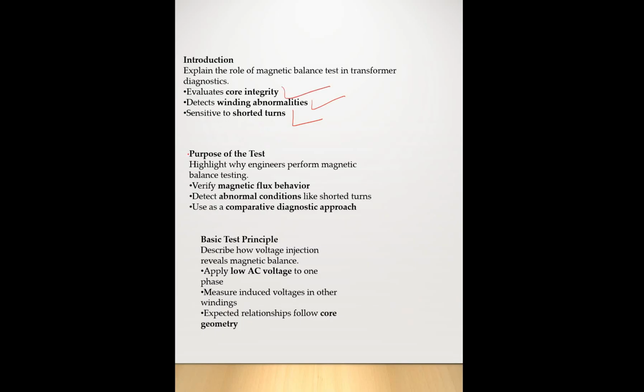Okay, and the purpose of this test is to highlight why engineers perform the magnetic balance test. The magnetic balance test is to verify magnetic balance and magnetic flux behavior and detect abnormal conditions like shorted turns, using a comparative diagnostic approach. The basic test principle describes how voltage injection reveals magnetic balance.